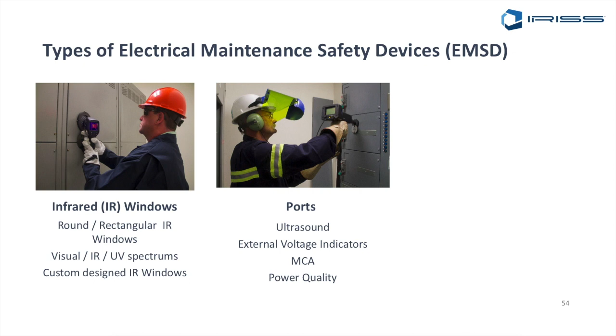There are also things like external voltage indicators, motor current analysis tap-off points, and power quality tap-off points. There are standards now looking at safety through design, where when we design equipment, we take every piece of data we need from it. We should be able to safely get that data with the equipment fully enclosed and guarded, routinely under full load conditions. That's what we're trying to achieve, and ports and windows are a big part of that.